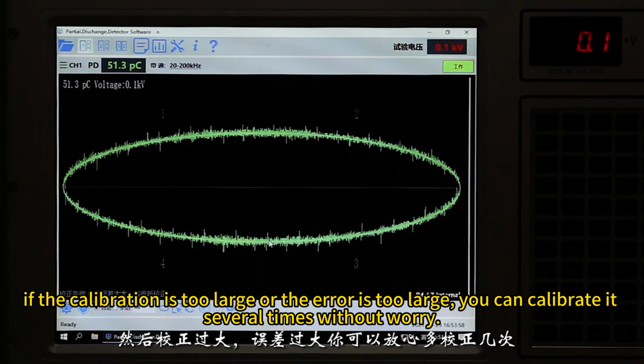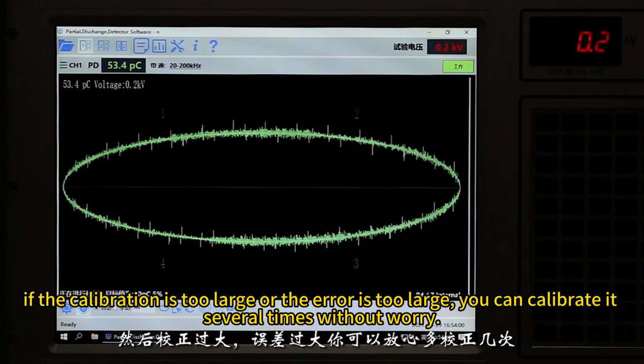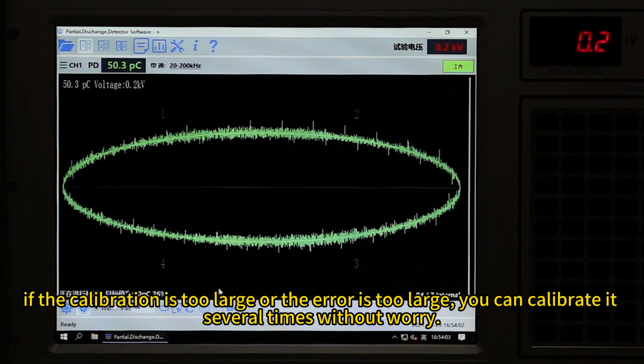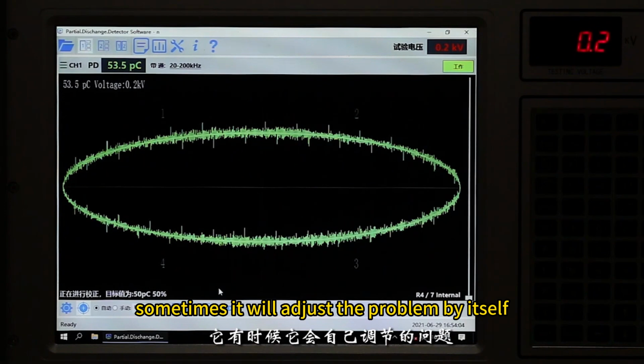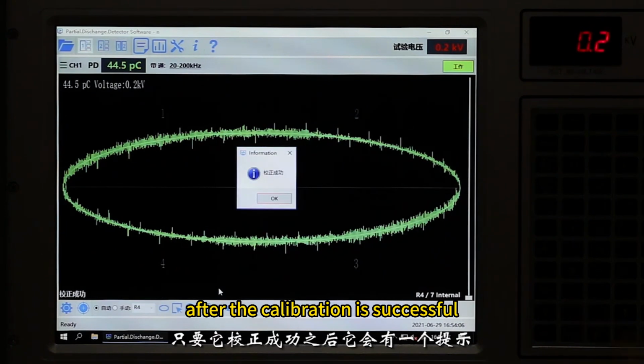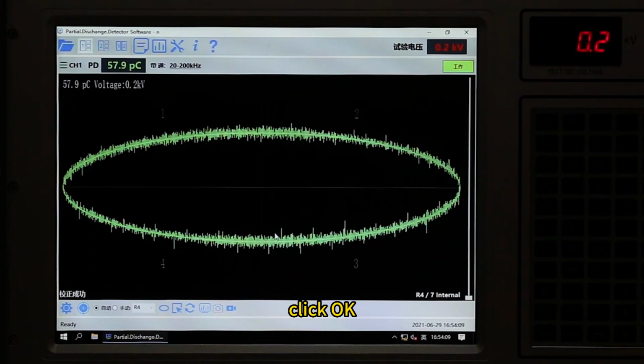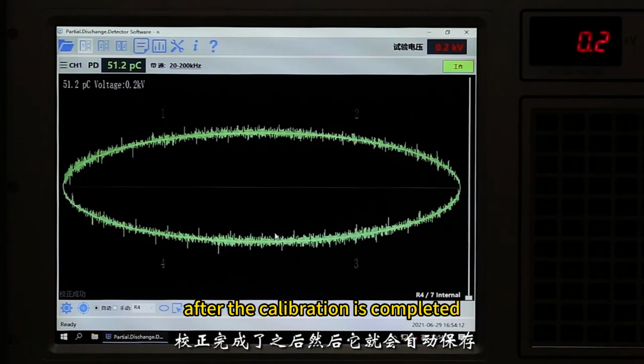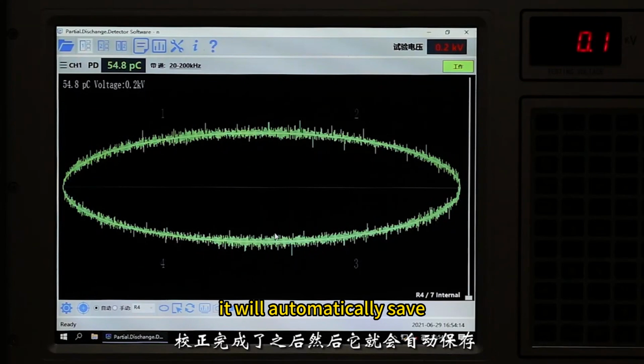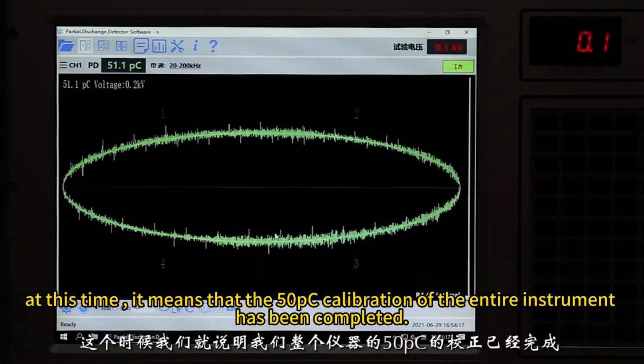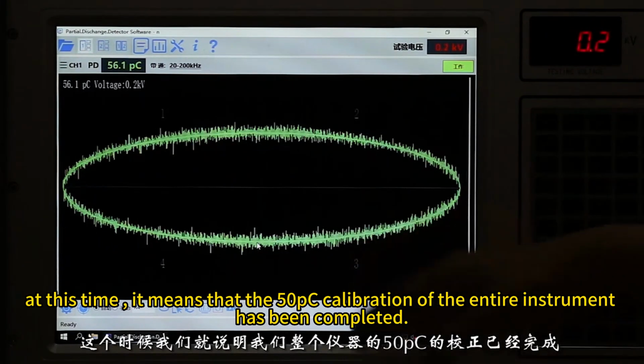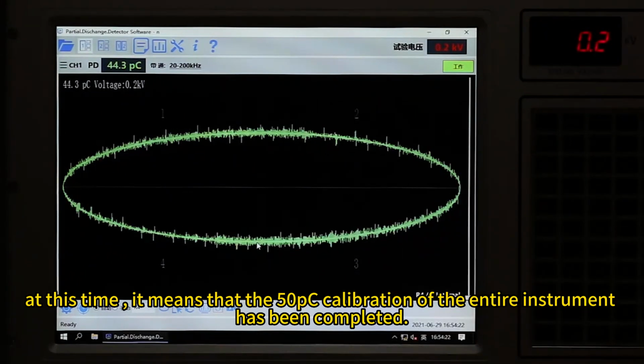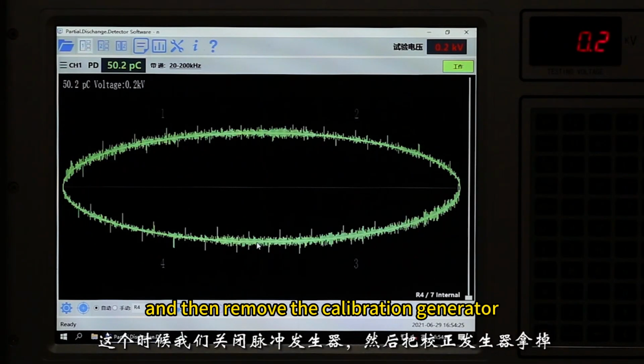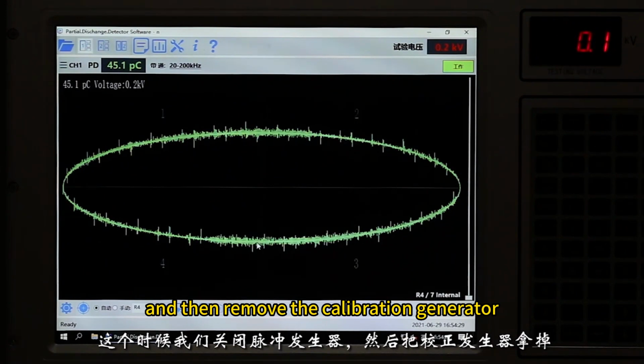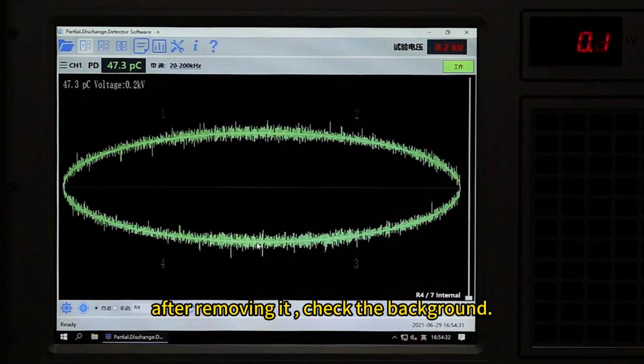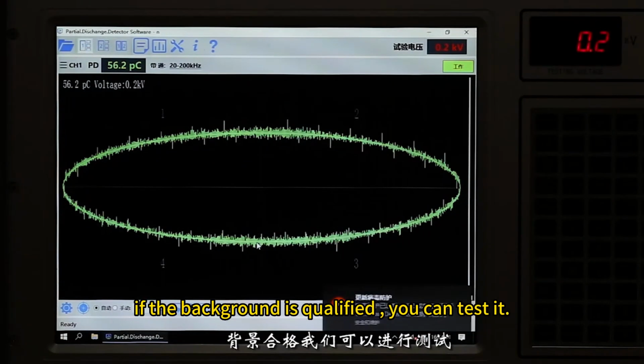If the calibration is too large or the error is too large, you can calibrate it several times without worry. Sometimes it will adjust the problem by itself. After the calibration is successful, it will have a prompt. Click OK. After the calibration is completed, it will automatically save. At this time, it means that the 50 pC calibration of the entire instrument has been completed. Turn off the pulse generator, and then remove the calibration generator. After removing it, check the background. If the background is qualified, you can test it.